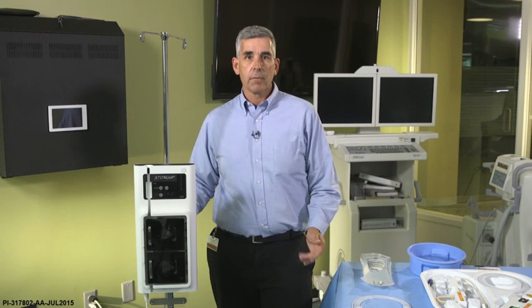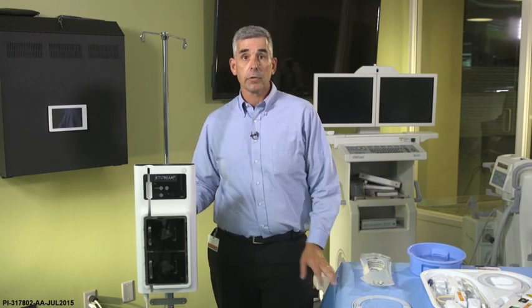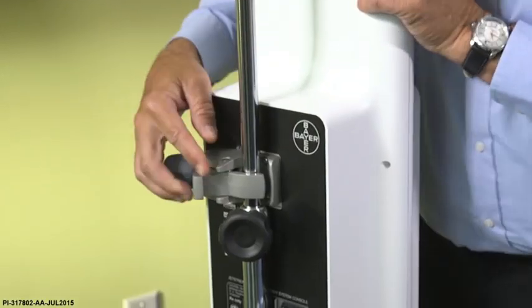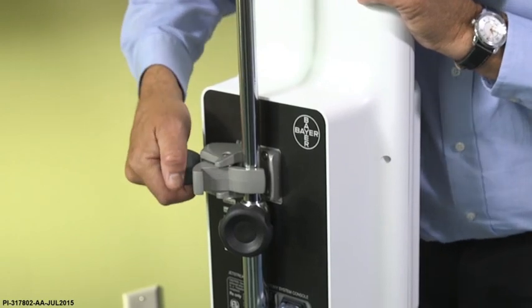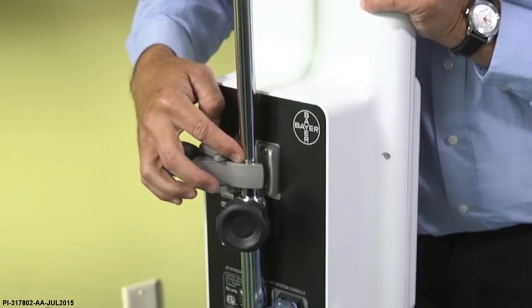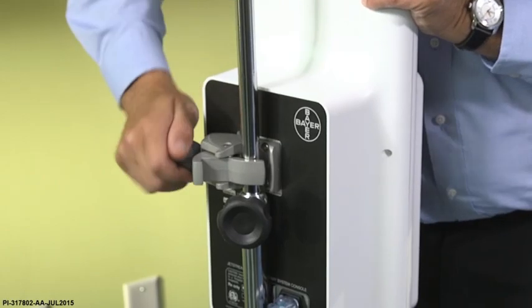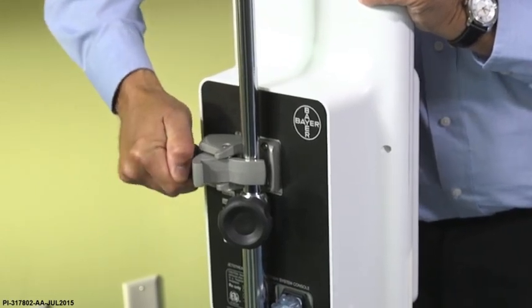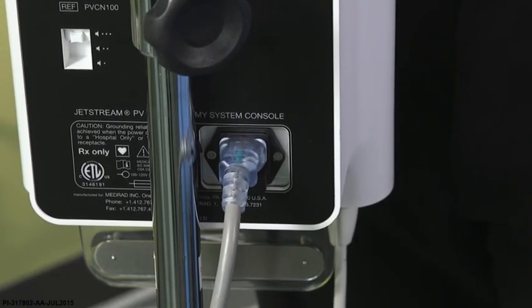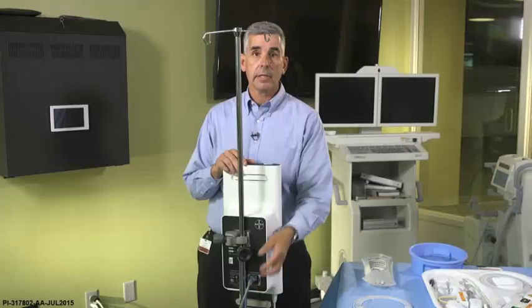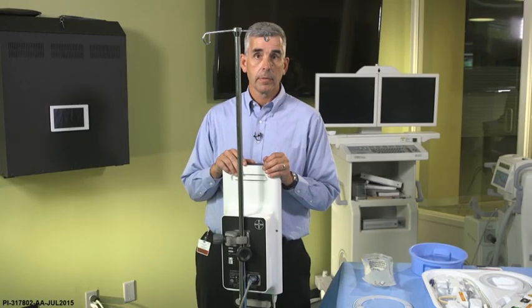When setting up the system, first you'll need to secure the Jetstream console to the IV pole. Simply loosen the clamp to a size that allows the clamp to slide over the IV pole. With the clamp on the pole, tighten the clamp to secure the console to the pole. The power cord is also located in the rear of the Jetstream. Simply plug into any standard 120 volt outlet.